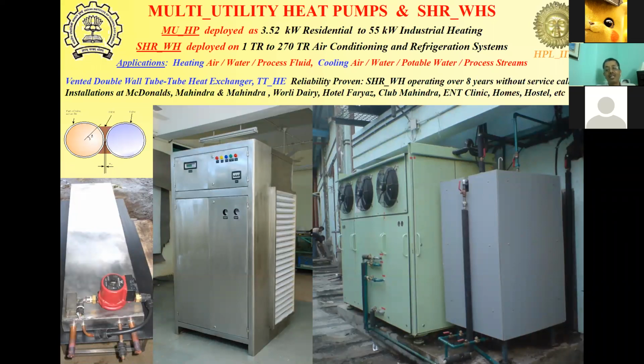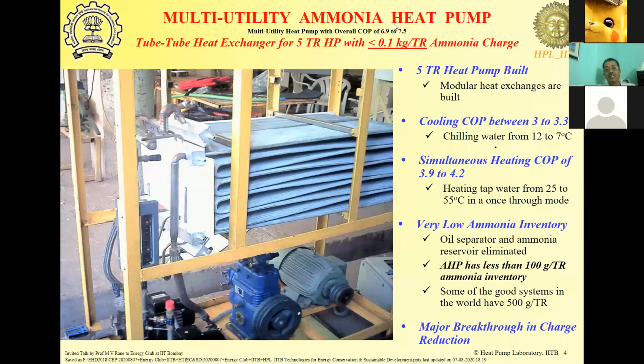In addition to that, because of the lower condensing temperature, the power consumption saving in this unit was around 25 to 36%. So this is one of the multi-utility heat pump applications. The tube heat exchangers also give us many advantages with respect to very low inventory of refrigerant in the system. Inventory of the refrigerant is important because some of the refrigerants cause ozone depletion. Some might be hazardous or toxic, like ammonia, which is flammable and toxic also. So if we can reduce the charge of ammonia, then using ammonia in many applications like commercial heat pumps, or even for air conditioning applications, will be feasible.